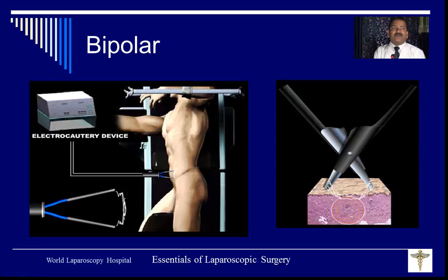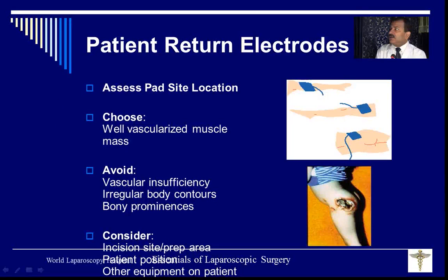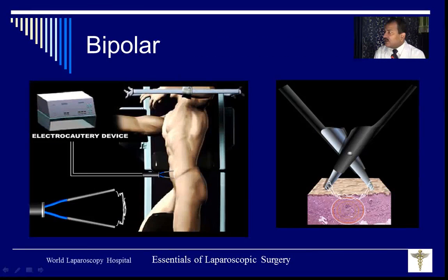Bipolar doesn't have these problems. Why? The scientists saw that when they brought the patient return plate very near to the target of dissection, remote injury was not there. So they thought, why not bring the patient return plate inside the body of the patient, to the target area? So when you switch the machine to bipolar, there is no need of attaching the patient return plate. Even if it is attached, it gets automatically disconnected. In bipolar, the same wire comes to one of the poles.